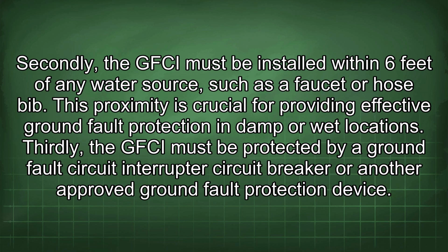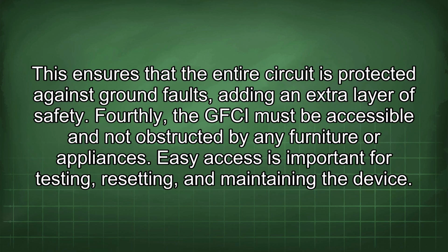Thirdly, the GFCI must be protected by a ground fault circuit interrupter, circuit breaker, or another approved ground fault protection device. This ensures that the entire circuit is protected against ground faults, adding an extra layer of safety. Fourthly, the GFCI must be accessible and not obstructed by any furniture or appliances. Easy access is important for testing, resetting, and maintaining the device.